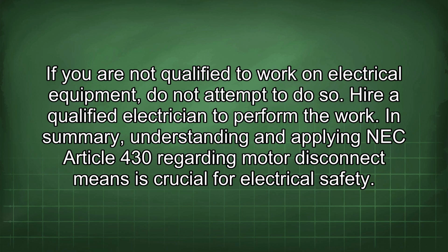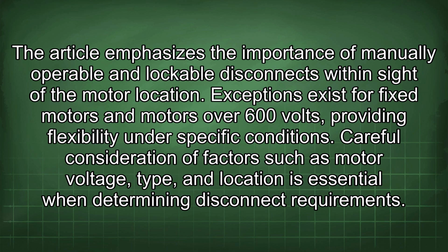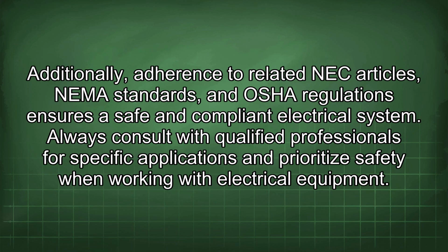In summary, understanding and applying NEC Article 430 regarding motor disconnect means is crucial for electrical safety. The article emphasizes the importance of manually operable and lockable disconnects within sight of the motor location. Exceptions exist for fixed motors and motors over 600 volts, providing flexibility under specific conditions. Careful consideration of factors such as motor voltage, type, and location is essential when determining disconnect requirements. Additionally, adherence to related NEC articles, NEMA standards, and OSHA regulations ensures a safe and compliant electrical system. Always consult with qualified professionals for specific applications and prioritize safety when working with electrical equipment.